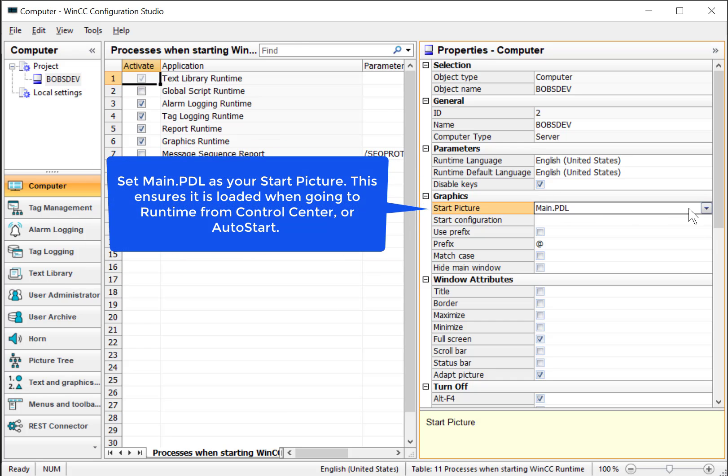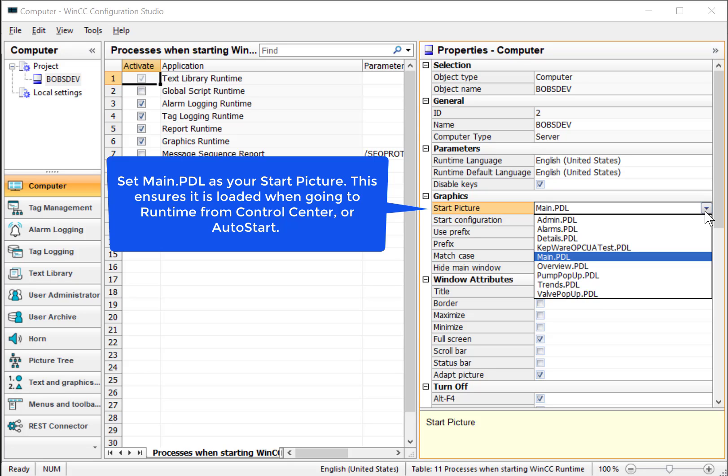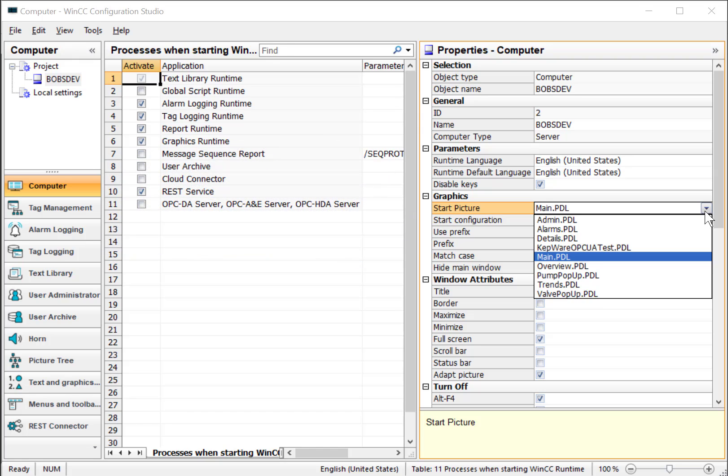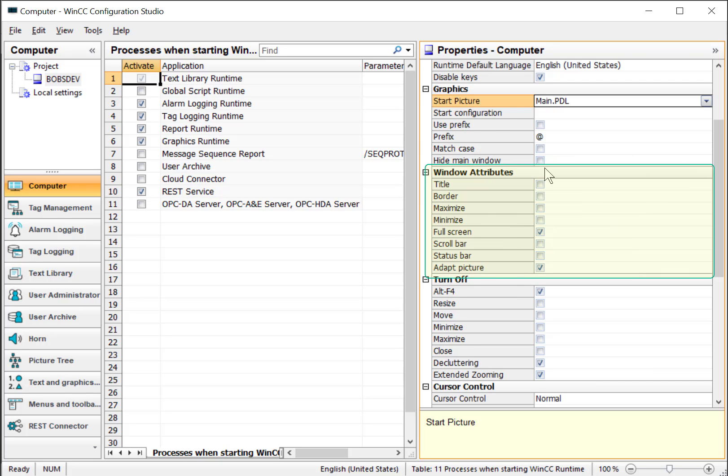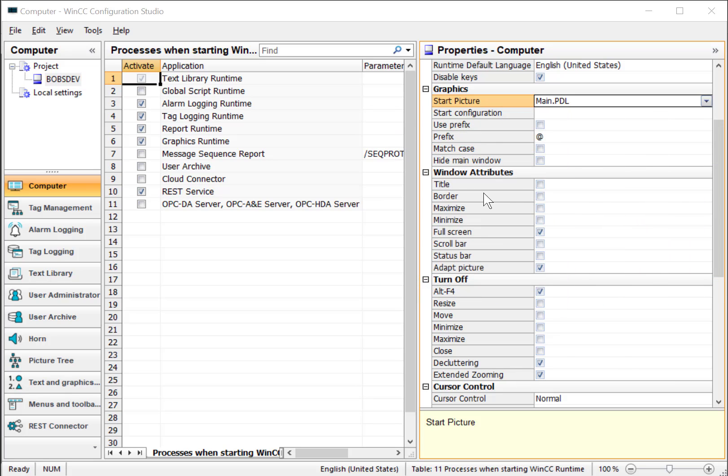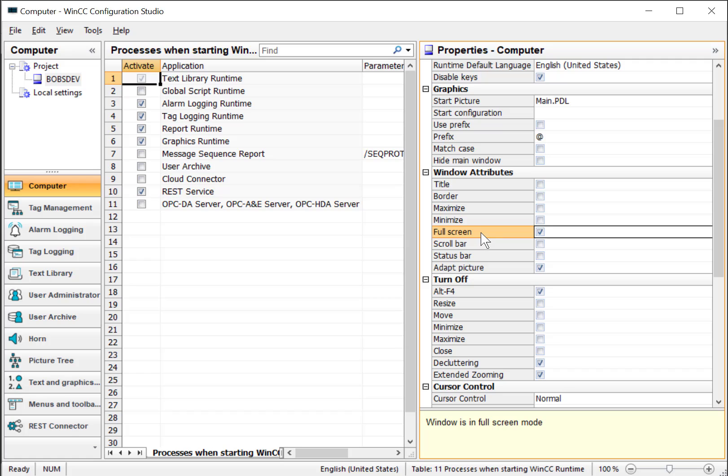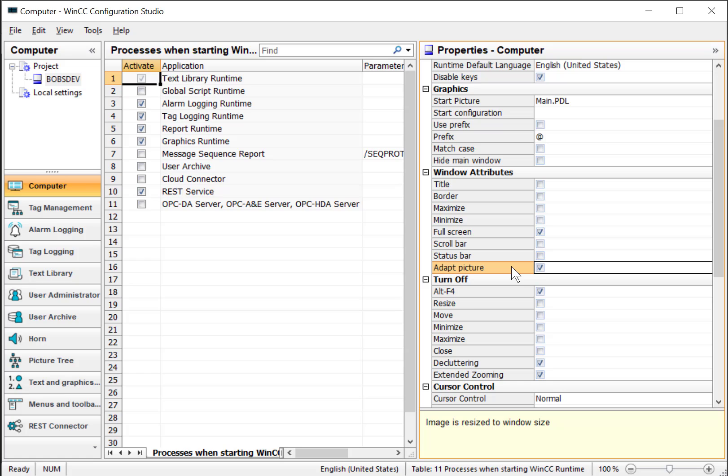You also want to make sure that your main PDL is your start picture. This is important because your logon controls are on your main screen. And when you go to runtime from Control Center or from the AutoStart application, this will be the page that's loaded. So make sure that main PDL is selected. Under Windows attributes, these are the attributes of the runtime window. So we don't want title or border checked. We want to check full screen. And this basically makes the runtime application fill the screen without a title or border or anything the user can move out of the way or resize to get back to the operating system. You probably also want to have Adapt Picture checked.